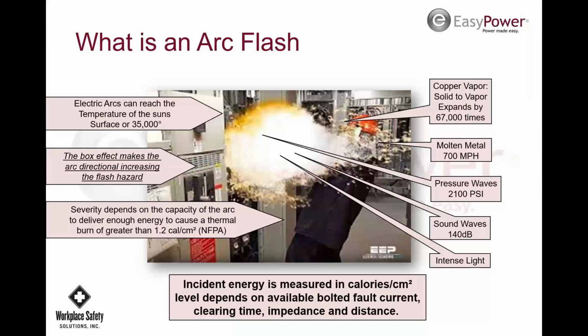It can. So then the other thing is clearing time. A breaker and a fuse has a certain amount of time that it will trip or it will open up. All breakers, all fuses, relays, every protective device has a time current curve, a certain amount of time and a certain amount of current. And that will trip in this bandwidth.